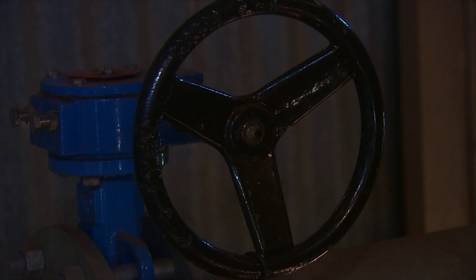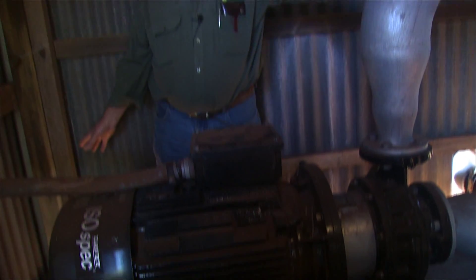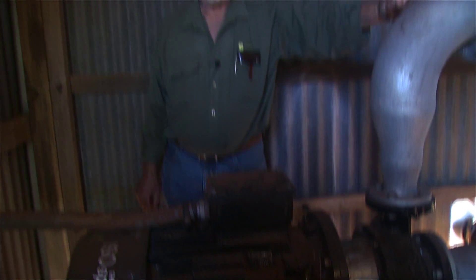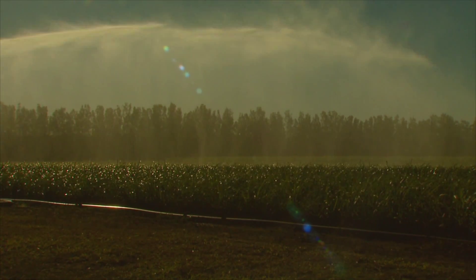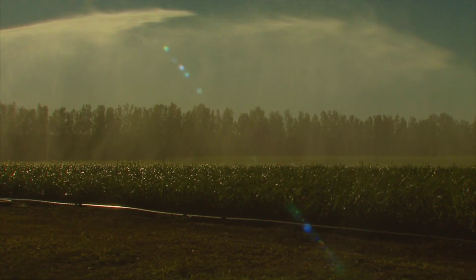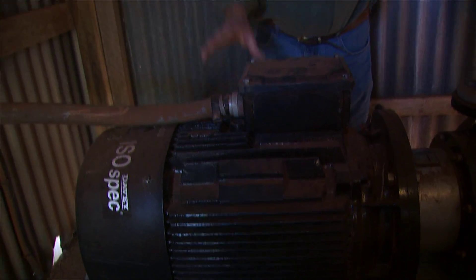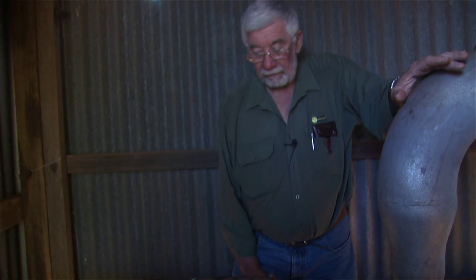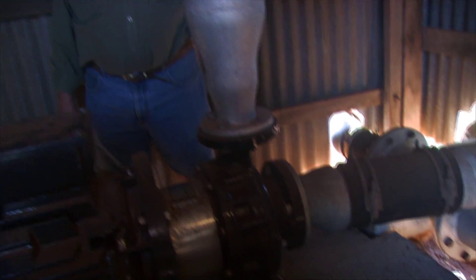Less energy is needed to pump water at a lower pressure, and a new, smaller pump has been installed that's partly solar powered. Previously, they were using two 60-horsepower or 42-kilowatt motors drawing roughly 80 kilowatts per hour to run two water winches. Those two winches watered the farm with roughly 50 millimetres every 14 days — and 14 days is simply too long in this environment. Seven days is about the right time between irrigation events. This motor now replaces those two. It's a 30-kilowatt motor drawing approximately 30 kilowatts per hour, driving a pump that pumps double the water of the two previous pumps at lower pressure.